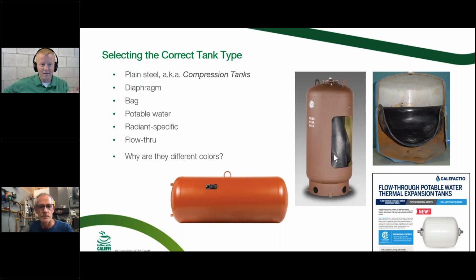Getting those bags out of there is a lot like wrestling an alligator, and a lot of times you need a block and tackle or some physical or mechanical means of actually getting it out of there. Don't think that they're necessarily the greatest thing sometimes, because most of the time they just get cut out and replaced anyways, but it's definitely something to consider, especially when you're looking for a full acceptance type situation. That would be a great source there, but just something to think about.